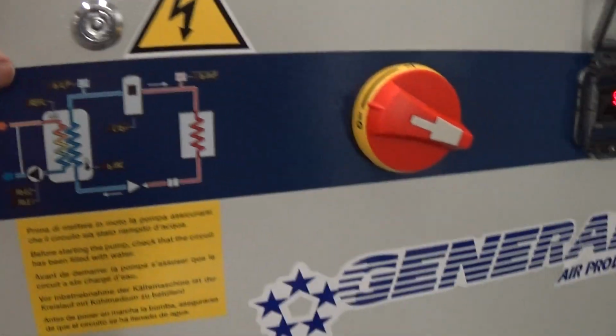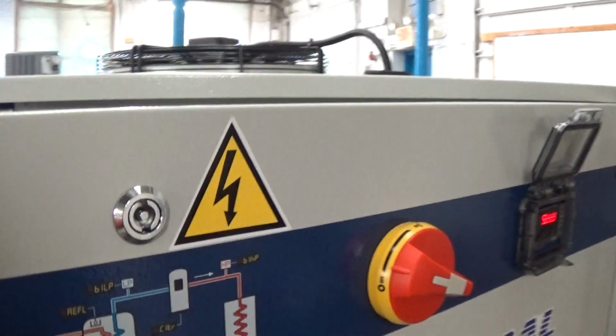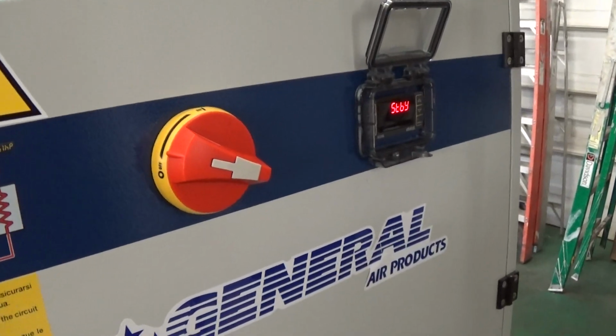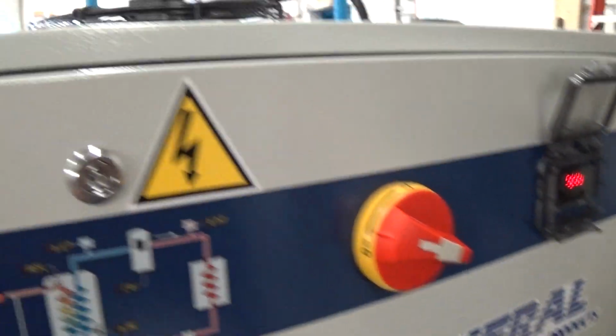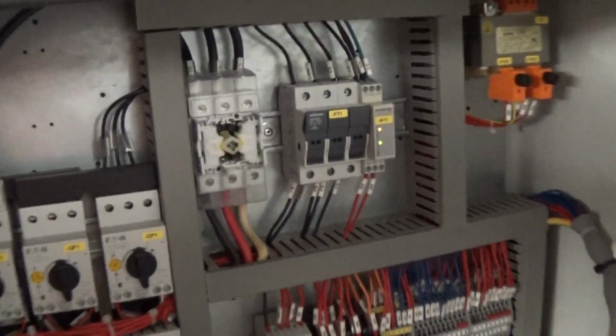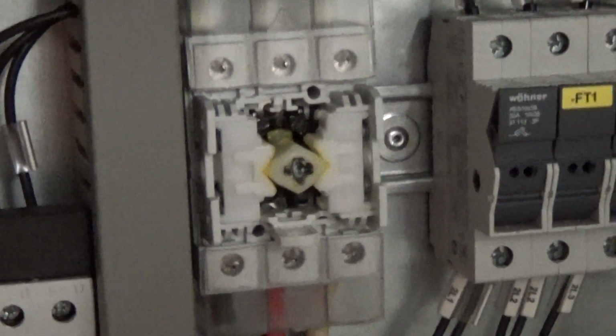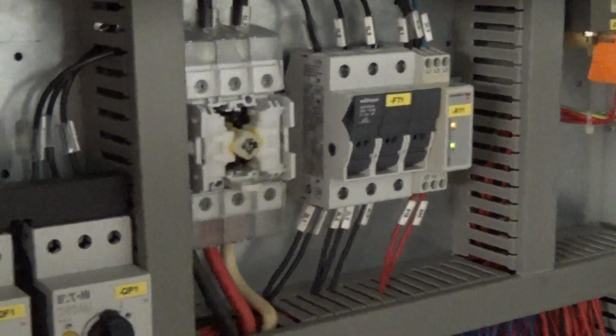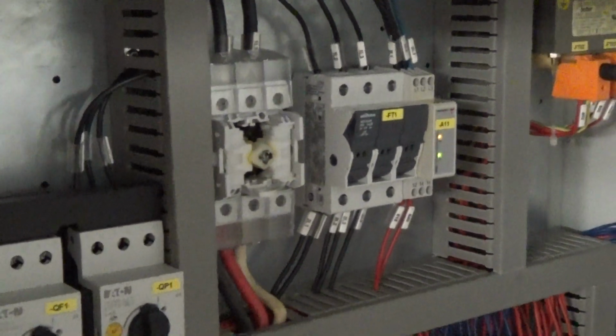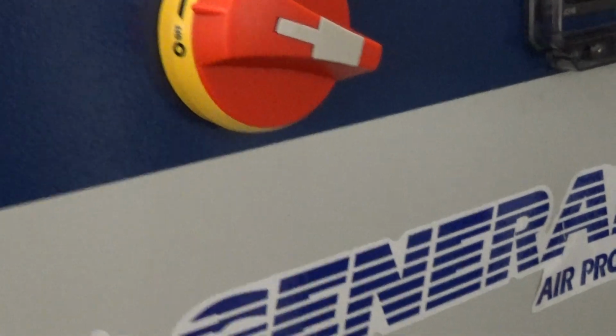The unit, in a test environment, we can open this door right now, but normally you'd have to turn that disconnect switch off, and then these two mechanical locks to open the door. One little accident we had is we snapped off the rod here on the rotary disconnect. We have a new one ordered. Under no circumstances whatsoever should you run the chiller without that new part installed, which we plan on installing, time permitting. We may have to drop ship that part, we'll see, depending on timing.